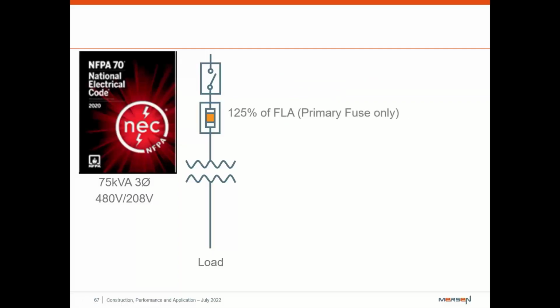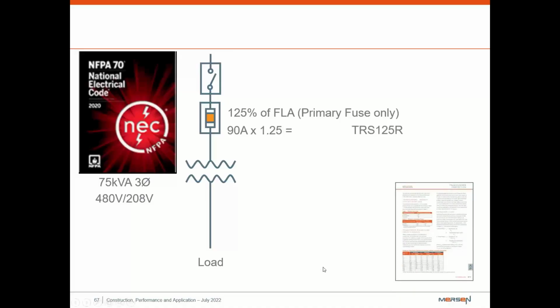So if you're only doing the primary fuses, you do 125% for primary only. So you take your 90 amps, multiply it by 125%, you're going to get about 112.5 amps. So the fuse we're going to use for this, you go the next size up, is going to be the TRS 125R. And again, we have literature on this. This will all be available to you, and it'll lay it out in a very clean manner. We'll actually tell you the kVA of the transformer, and then you just go along the side to what you're actually protecting.